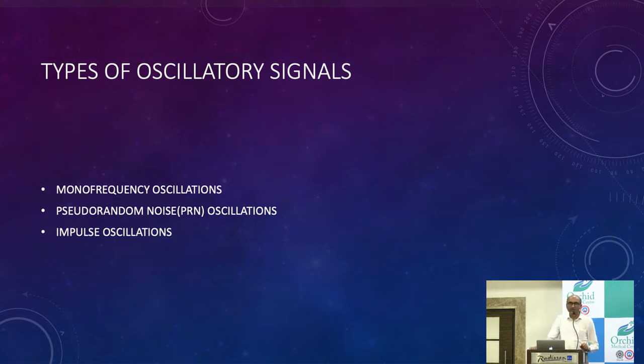Or it could be a series of sound waves sent inside the airways at various frequencies, maybe 5, 10, 12, 20, 25 hertz. When all these sound waves come back, the computer calculates the variations in flow caused by each individual sound wave. This is what we call pseudo-random noise oscillations, or PRN oscillations.